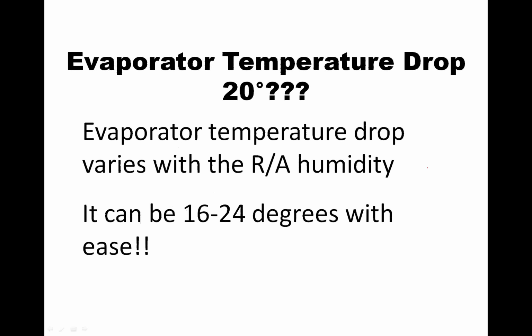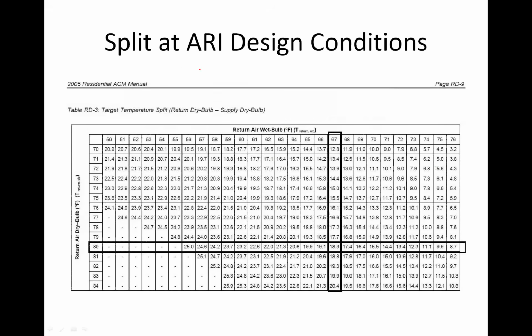The thing about evaporator temperature drop at 20 degrees, forget about it, because it's not right. The evaporator temperature drop varies with relative humidity, and that could be anywhere from 16 to 24 degrees with ease. If we look at this, this is a split chart. Again, it's page RD9. You can download this off our site for free. We have a link to it. This shows us what the split should be.